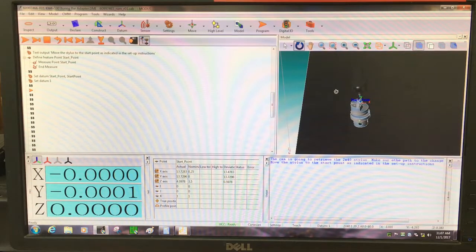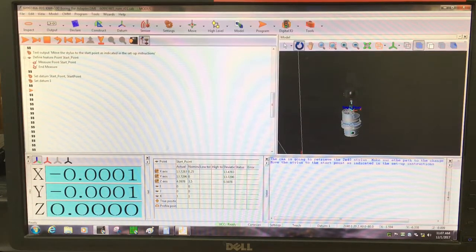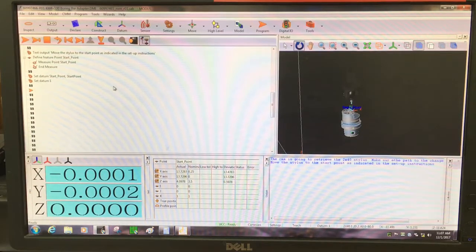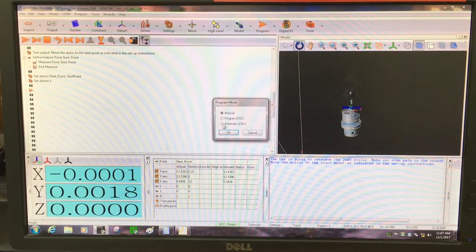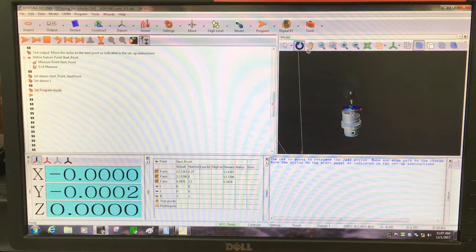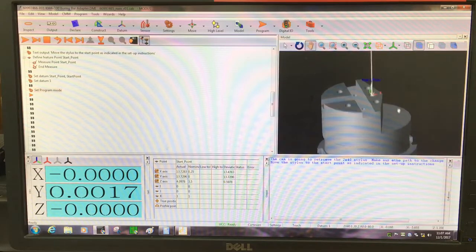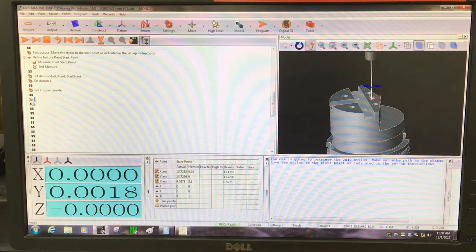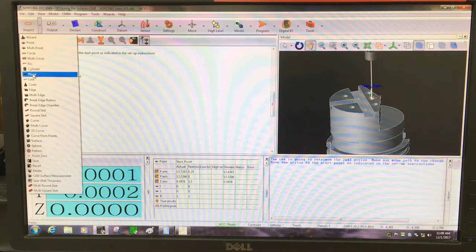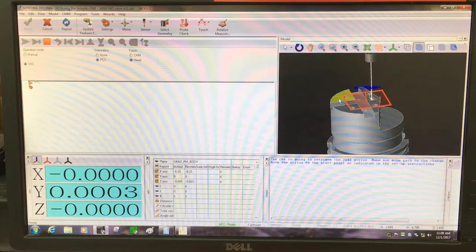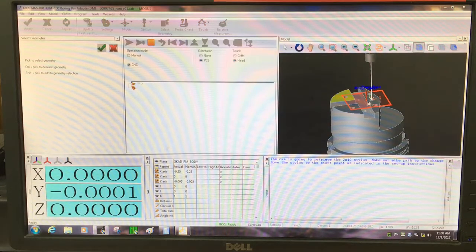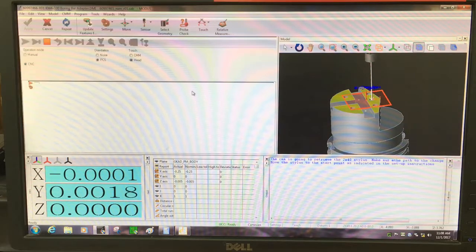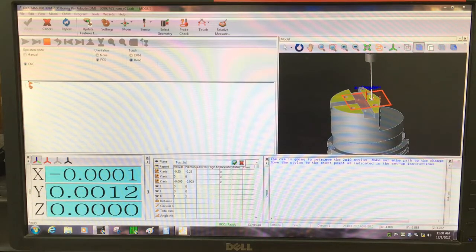Now we've told the computer and the CMM where the part is, but it has not actually touched the part yet. So now we're going to actually have it do program measurements. We're going to change settings mode to program. Always save. The first thing I'm going to do is touch up on the top to create a datum plane for that. Double-click on the dollar signs over here, spacing it out. Go to inspect plane. I'm going to select this plane - they're all in the same surface, so selecting this one you can still touch off on any of these surfaces. You can also select additional geometry and I can light them all up, but it really doesn't make much of a difference there. I'm going to name that top surface.